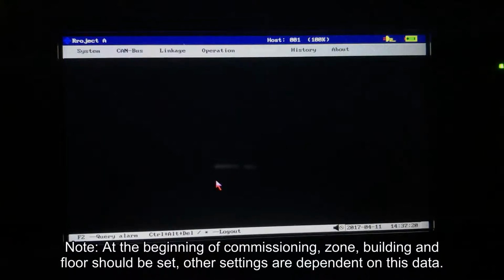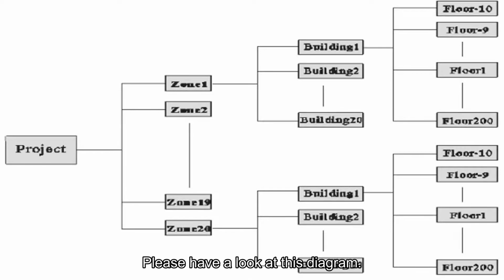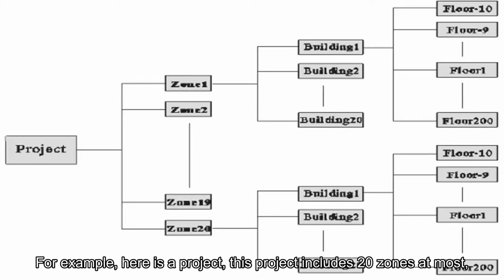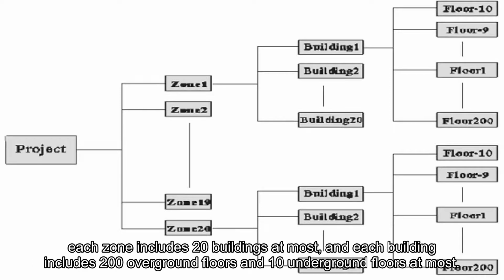Note: at the beginning of commissioning, zone, building, and floor should be set. Other settings are dependent on these data. Please have a look at this diagram. For example, here is a project. This project includes 20 zones at most. Each zone includes 20 buildings at most, and each building includes 200 overground floors and 10 underground floors at most.